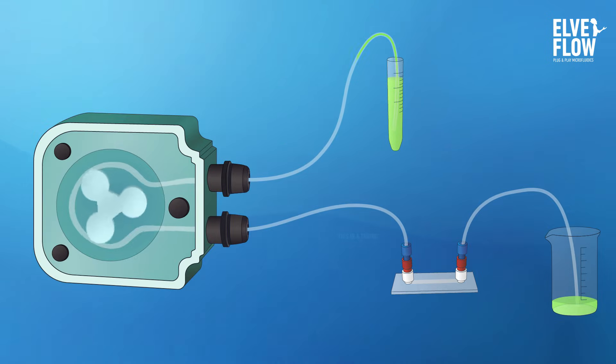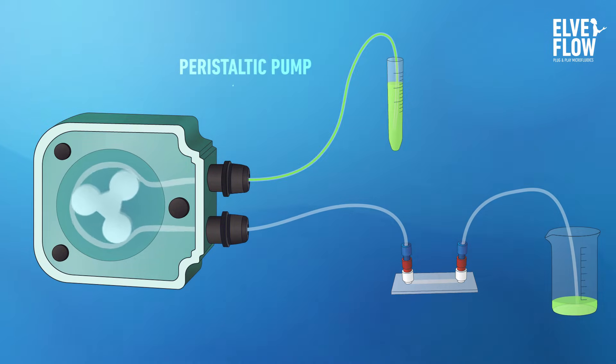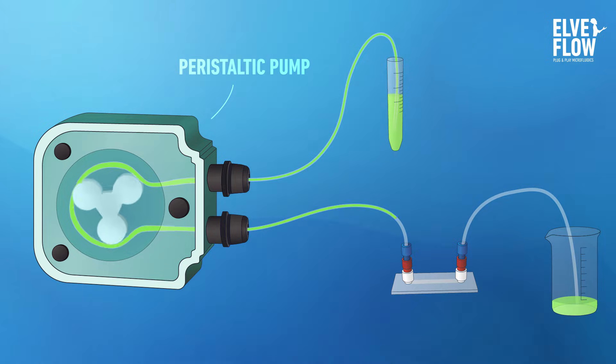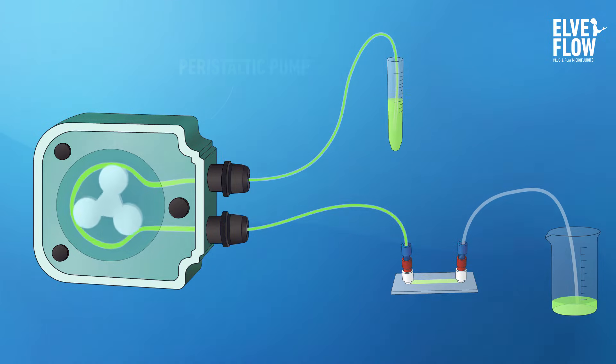The first method uses a peristaltic pump. This instrument applies a mechanical action onto a flexible tube to push the liquid flow from the tubing entrance to the exit.